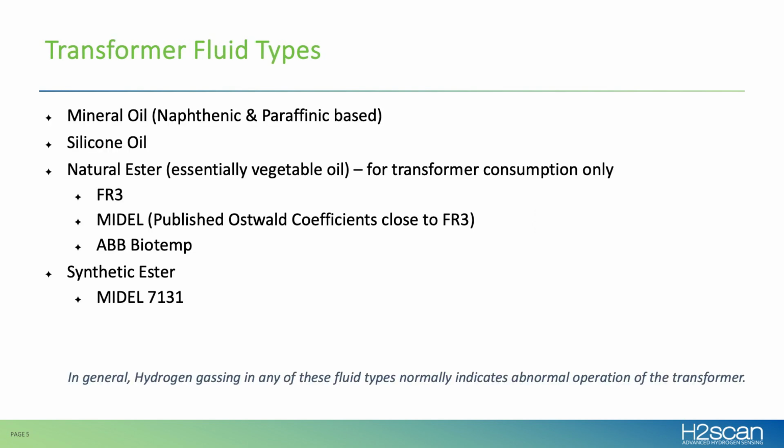Just to be a little clear on the various fluids, historically, manufacturers have used mineral oil in anywhere from large power transformers all the way down to distribution and instrument transformers. And still today, my guess is probably 95% of what you see out in the field is going to be filled with mineral oil.